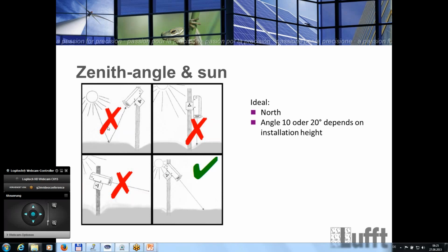But we saw in the past, when we developed the sensor 5-6 years ago, we made some tests in high mountain areas above 3-4 kilometers height in Austria, together with the people from the Austrian Meteorological Institute, and they found out that we have some limits when the global radiation is getting too high and is reflected from a snow surface, very dry snow with ice crystals.